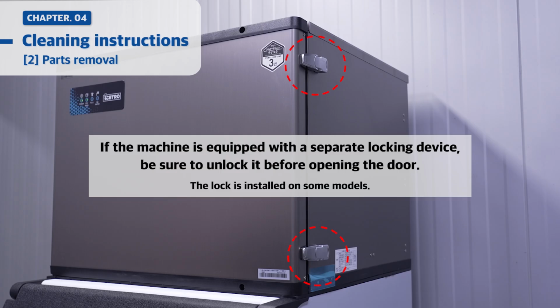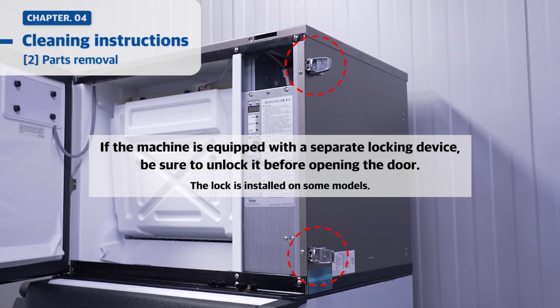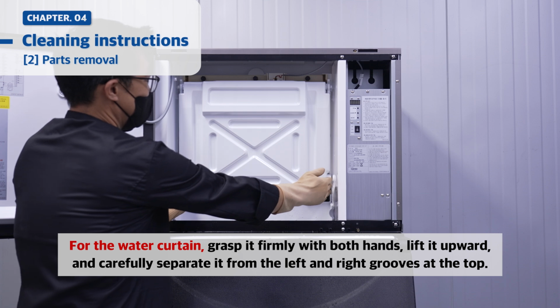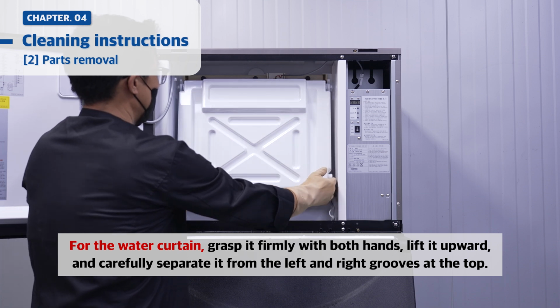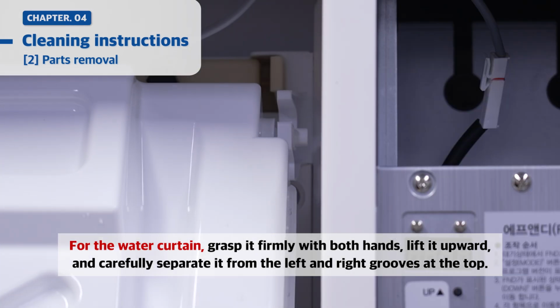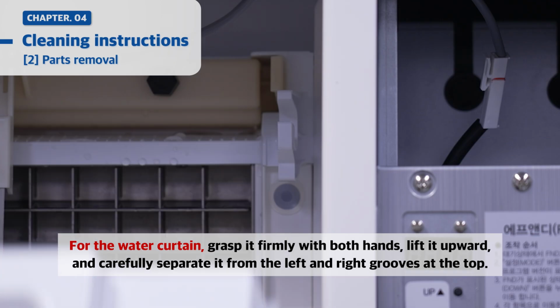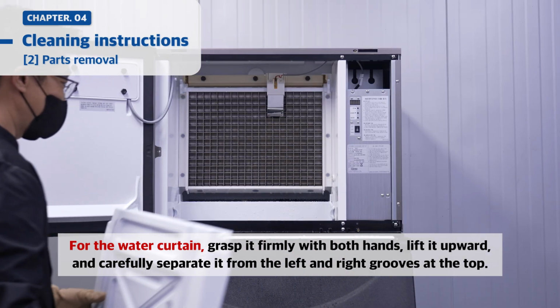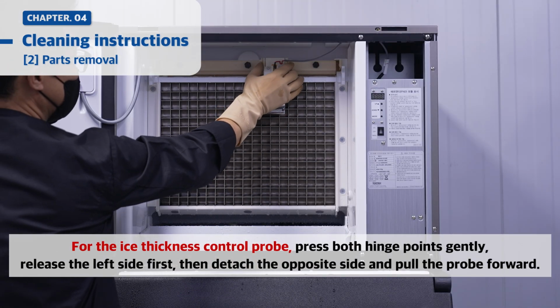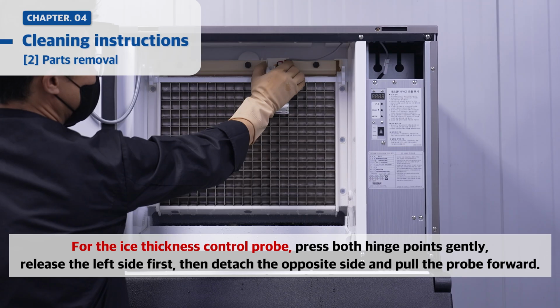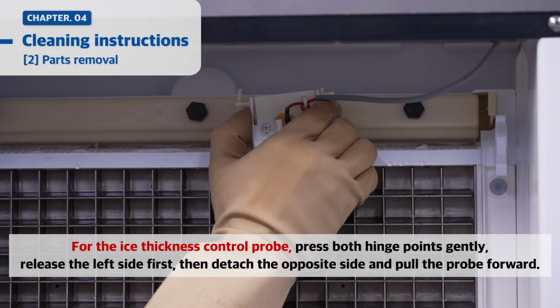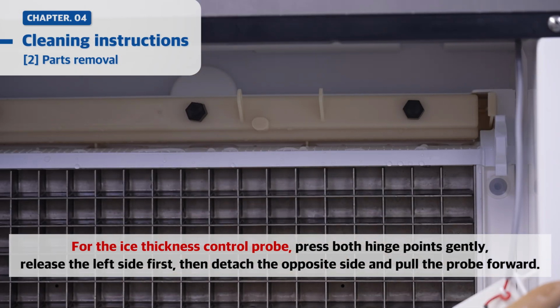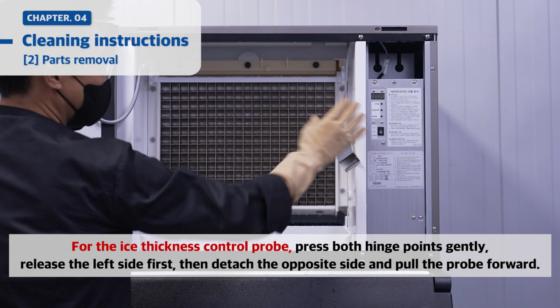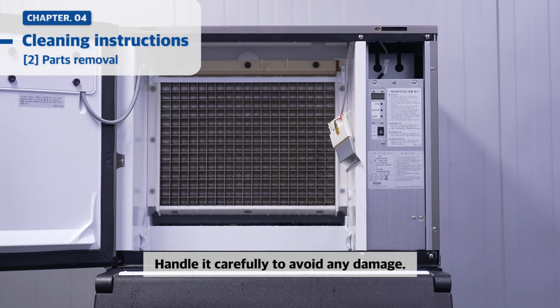If the machine is equipped with a separate locking device, be sure to unlock it before opening the door. For the water curtain, grasp it firmly with both hands, lift it upward, and carefully separate it from the left and right grooves at the top. For the ice thickness control probe, press both hinge points gently, release the left side first, then detach the opposite side, and pull the probe forward. Handle it carefully to avoid any damage.